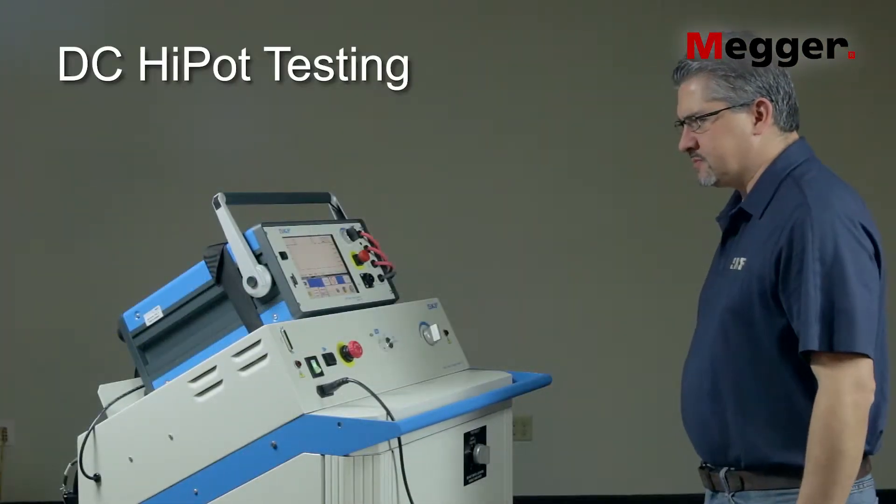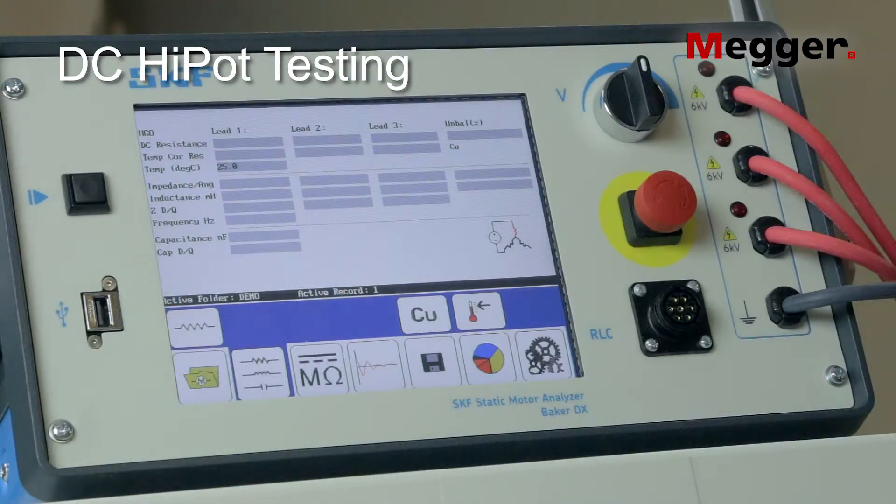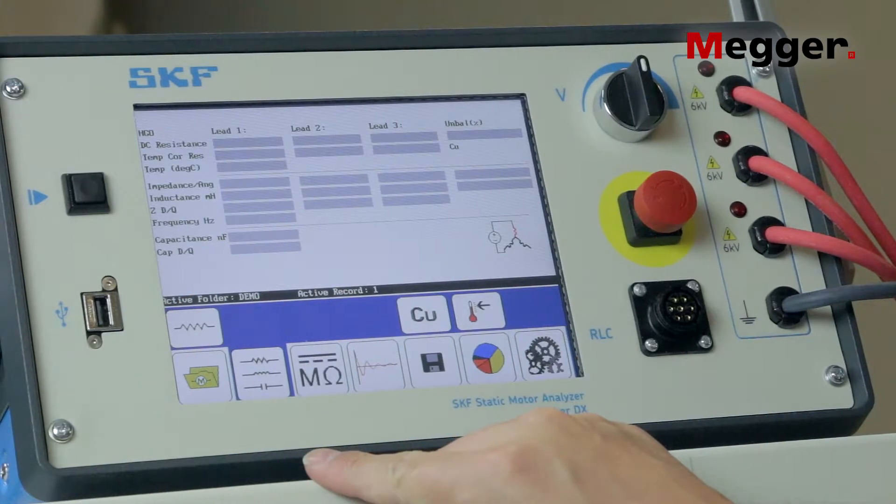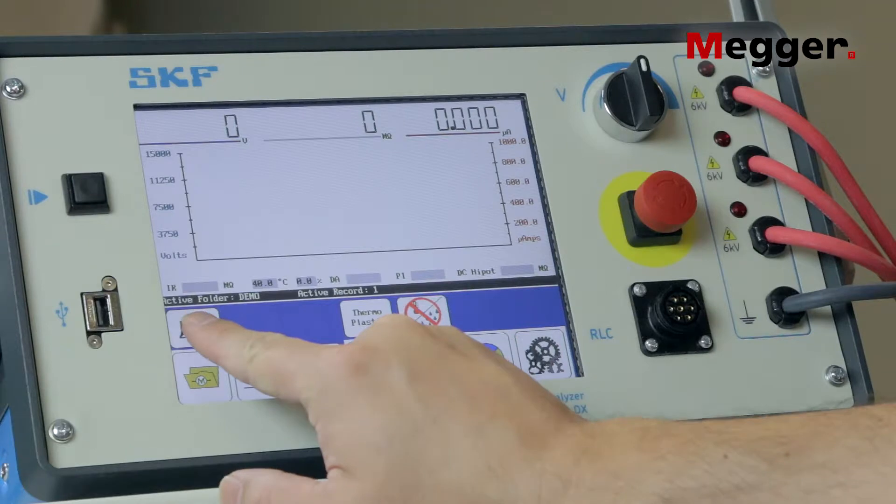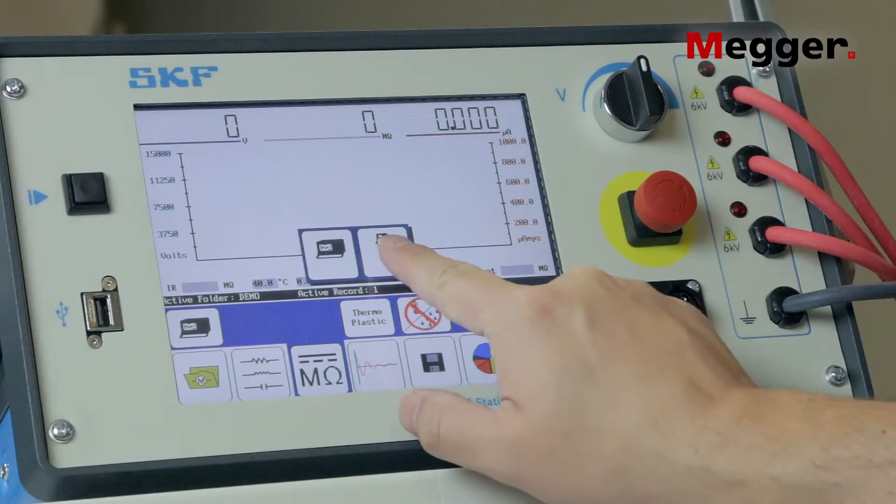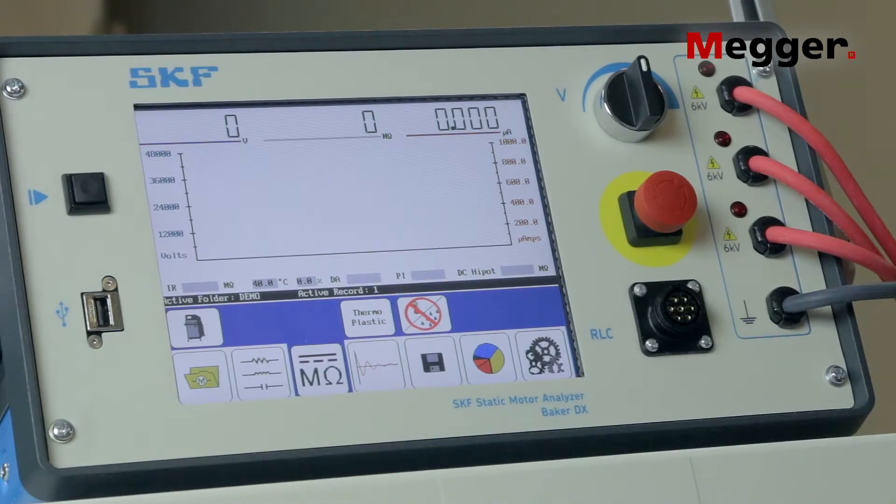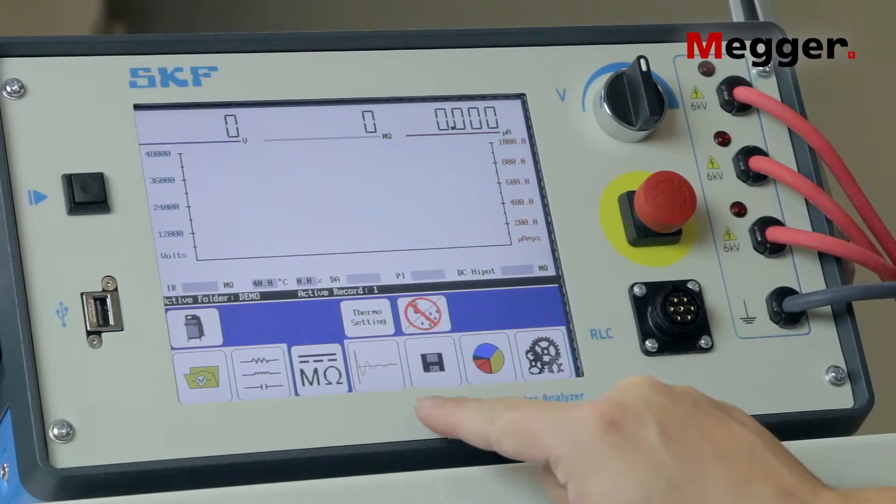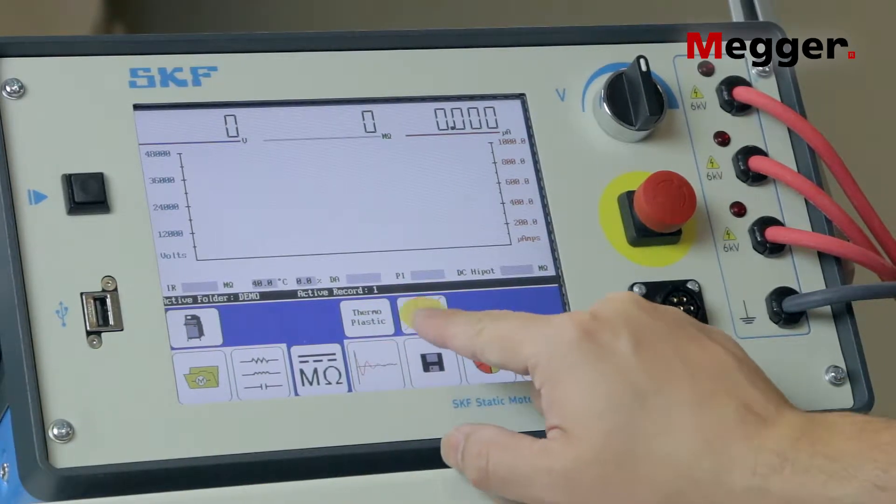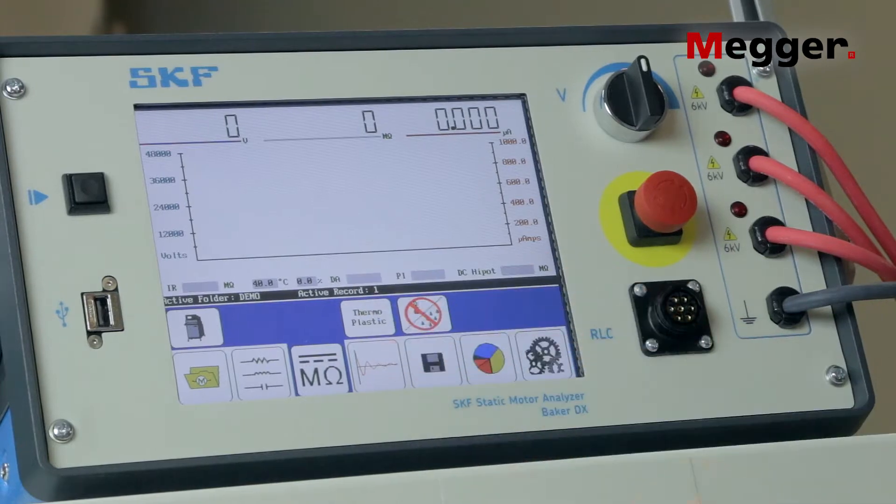Let's start with DC high pot testing. On the main screen of the DX, select the DC test. Select the power pack configuration. Select either thermoplastic or thermosetting corresponding to the type of insulation being tested. Enter the stator winding temperature.